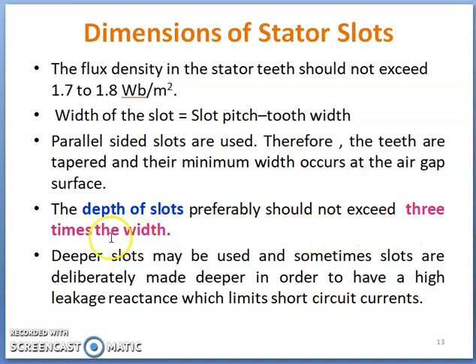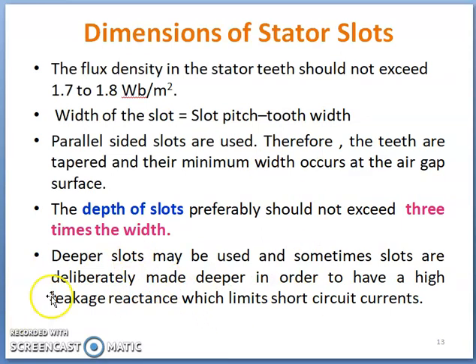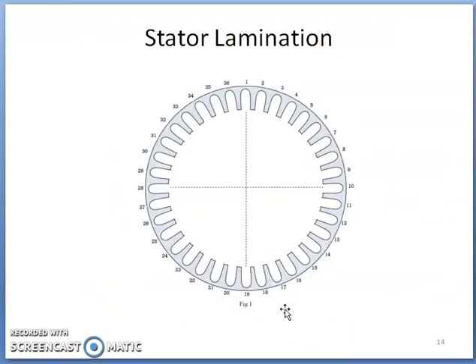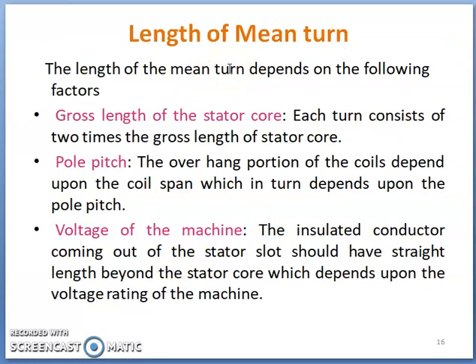The depth of the slot should not exceed three times its width. When deeper slots are used, leakage reactance becomes very large, which limits short-circuit current under transient conditions. In the case of salient pole machines, as the internal diameter is quite large, flux density along the depth of the tooth does not vary appreciably, and the width of the tooth may be estimated corresponding to the permissible flux density at the middle section of the tooth, which should not exceed 1.8 Wb/m².